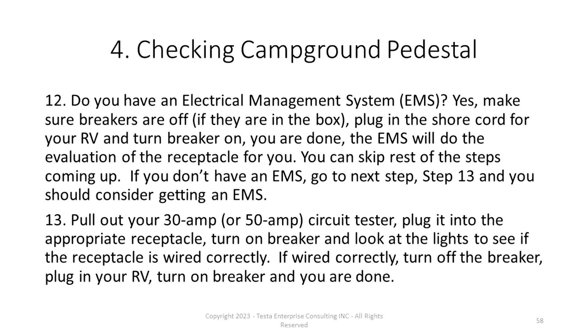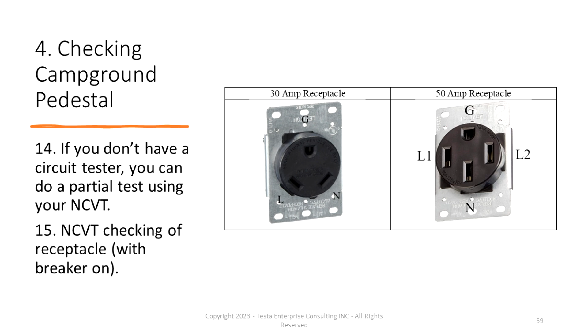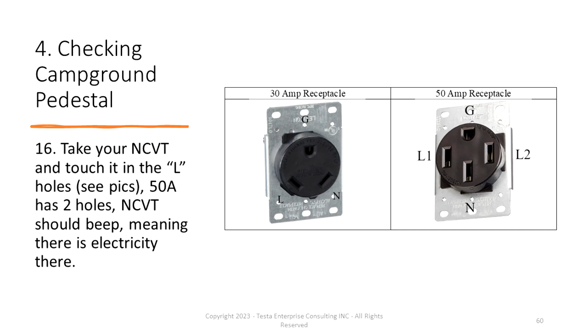Step 14, if you don't have one of those circuit testers, you can do a partial test using your NCVT. Take your NCVT and check the receptacle with the breaker on. Look at the picture here: there's a 30 amp receptacle on the left with an L pointing to one of the holes on the receptacle, and if you have a 50 amp receptacle, you have both an L1 and L2. Those are the ones you're going to want to put the NCVT in to start with, to see if there's electricity.